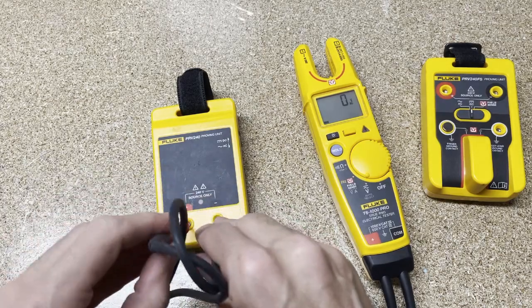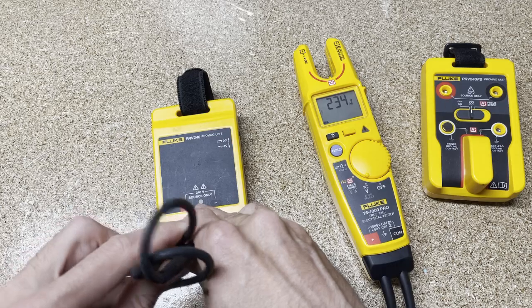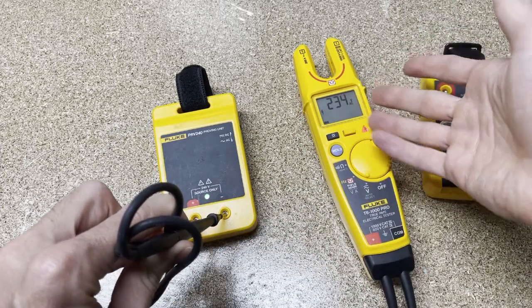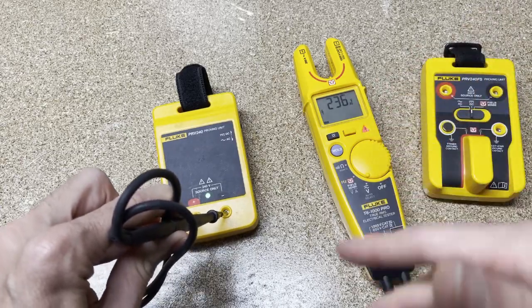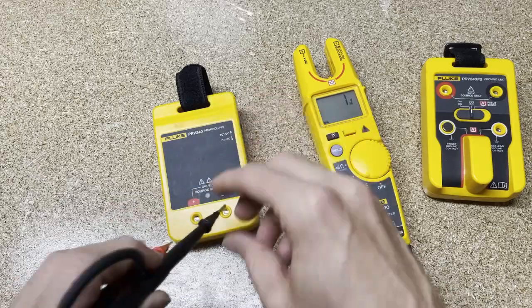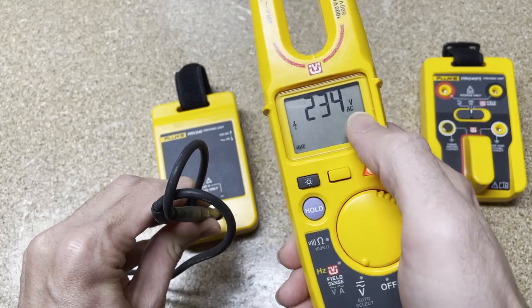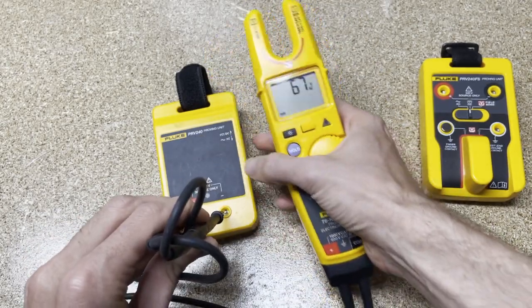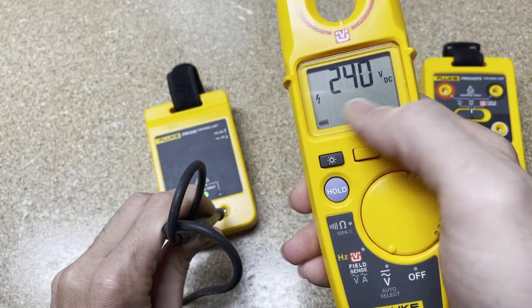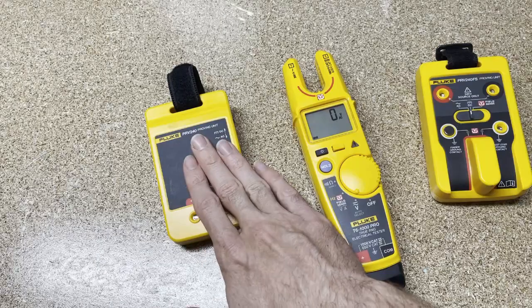Red on red, black on black — you push down, you'll see a green LED light turn on over here. This one's not quite 240 volts, but it's close enough. That's what you want — it doesn't matter that it's exact; what matters is that you are getting AC voltage. Let's look at that one more time: push down, you see AC voltage. Now I toggle it and do the same thing — DC voltage. That is the proving unit.